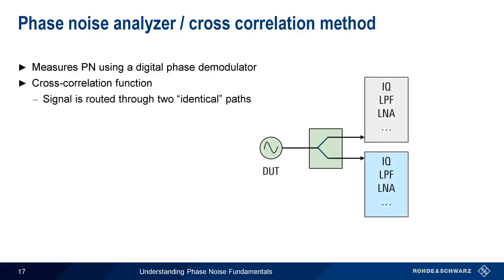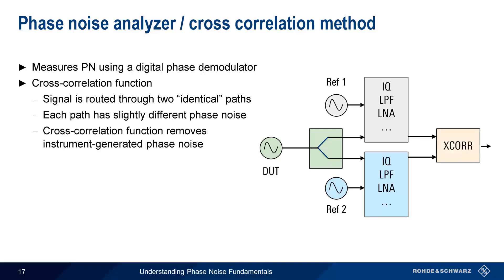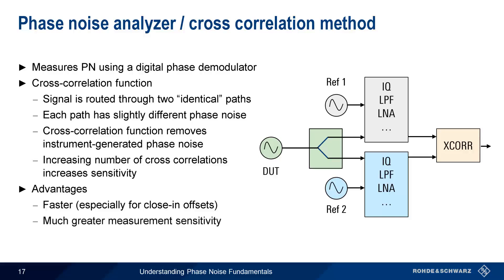Although it presents results in the same way, a phase noise analyzer measures phase noise differently than a spectrum analyzer. The first difference is that phase noise analyzers measure phase noise directly, typically using a special digital phase demodulator. The other important difference is related to the cross-correlation function in modern phase noise analyzers. In cross-correlation, the incoming signal from the DUT or device under test is routed through two identical measurement paths in the instrument. These identical paths have independent oscillators, each of which has slightly different or uncorrelated phase noise. These two paths feed a cross-correlation function that can then remove the uncorrelated phase noise generated by the instrument, allowing a more precise and more sensitive measurement of the phase noise in the signal from the DUT. Increasing the number of cross-correlations further increases the sensitivity, allowing the measurement of extremely low levels of phase noise. Phase noise analyzers therefore have the advantage of being much faster, especially when measuring close-in offsets, as well as having much greater measurement accuracy and sensitivity.